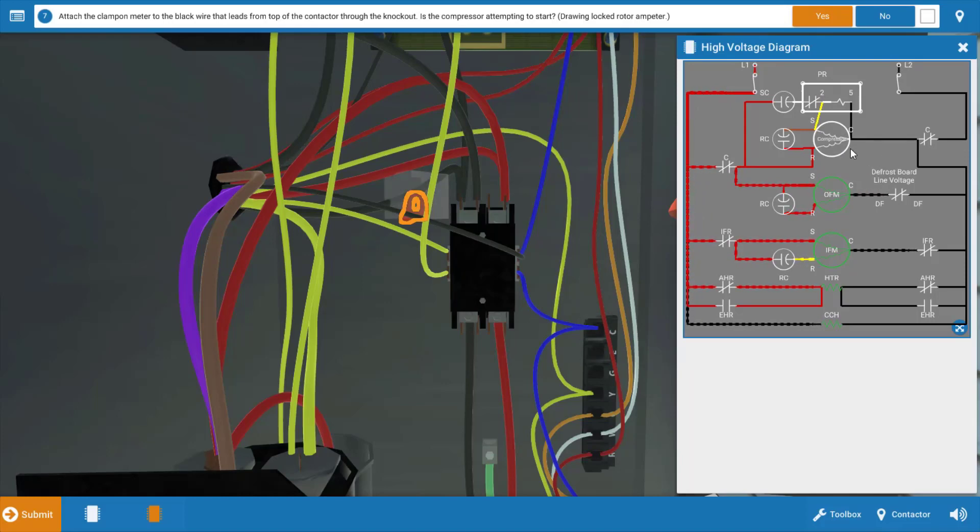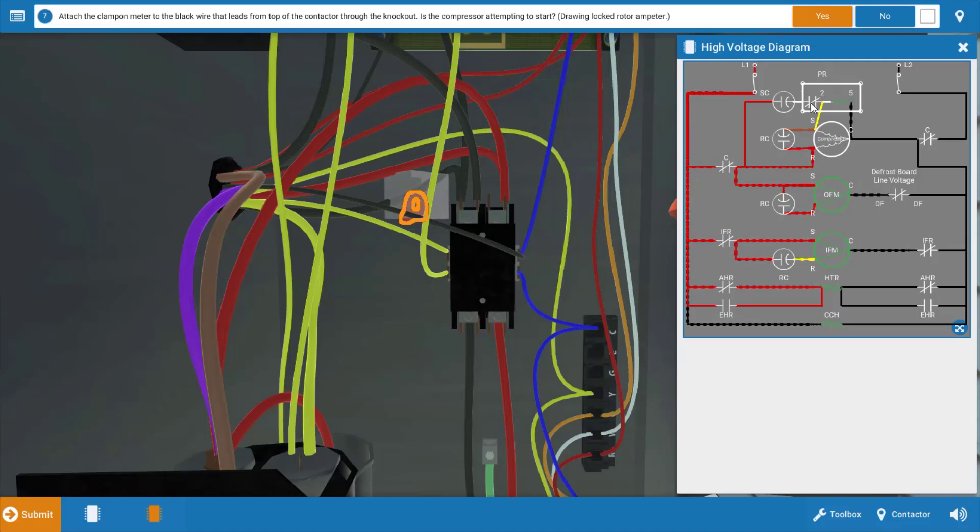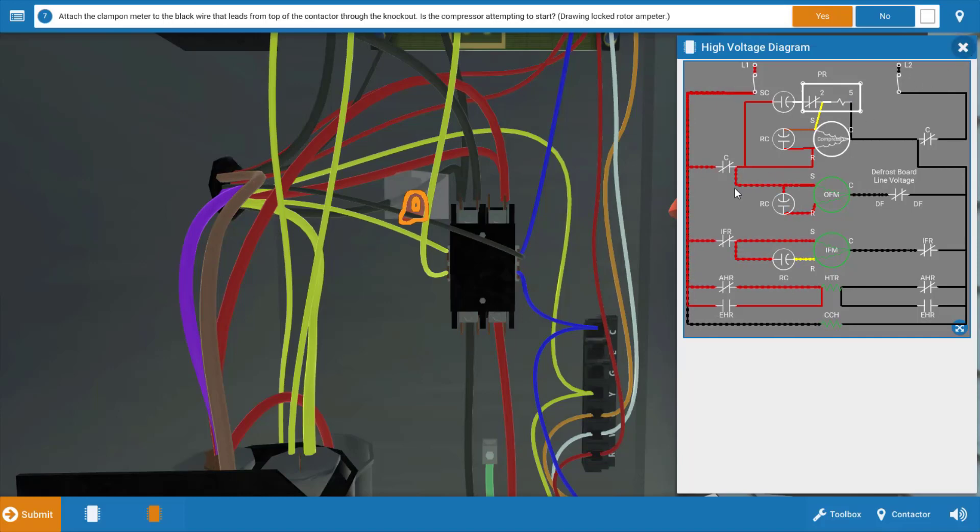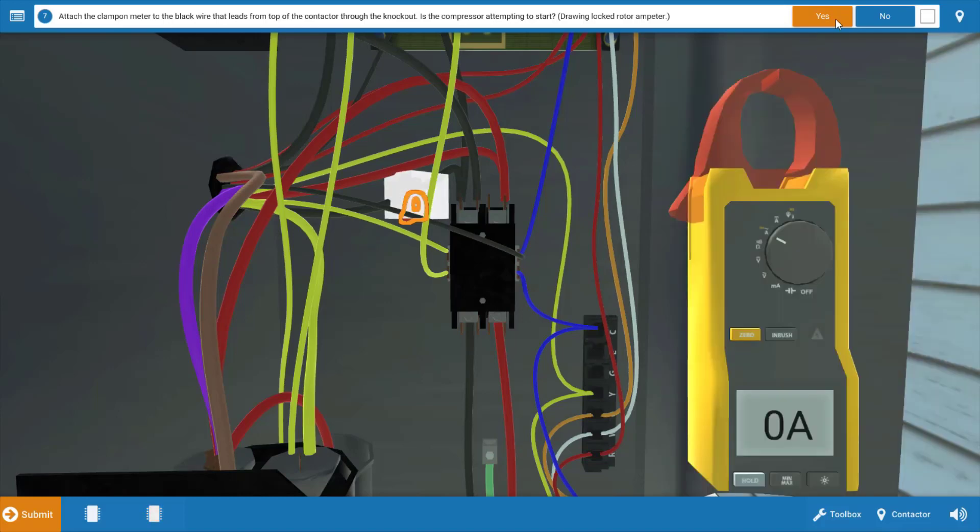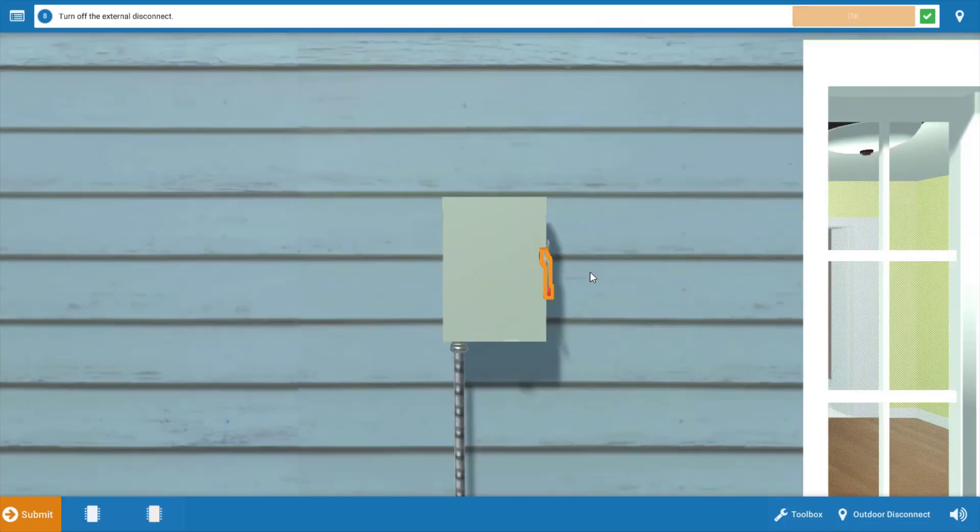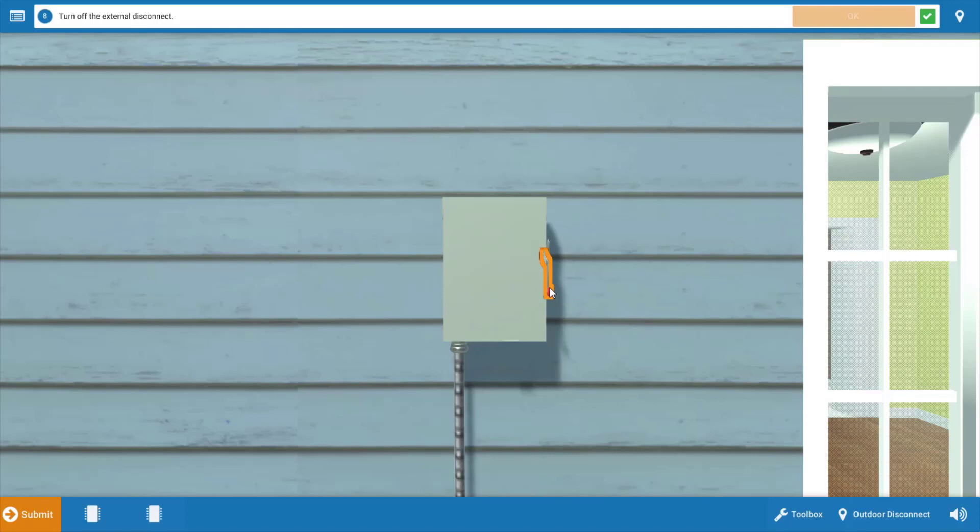Again, we're looking at the compressor motor itself, possibly an open winding, a faulty set of contacts in the potential relay, or one of our capacitors. So I'm going to store the wiring diagram away. We're going to click yes in the procedure guide that it drew locked rotor amperage. And we're going to need to measure resistance and then capacitance here. So we're going to need to turn the power off. Click on the disconnect to turn the power off and click OK.